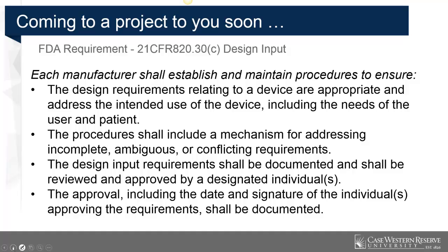Basically, when you think of the FDA requirement 820.30(c) about design input, you have to remember that brainstorming is more than just something we kind of do for fun. The manufacturer shall establish and maintain procedures. So brainstorming is a procedure to ensure, not insure, but to ensure that the design requirements are appropriate, and address the intended use of the device. Understanding the intended use is not something we do in isolation. Do it as a team, and in this, of course, we make sure we can do this through the mechanism of brainstorming in terms of creative aspects to identifying all the design requirements.